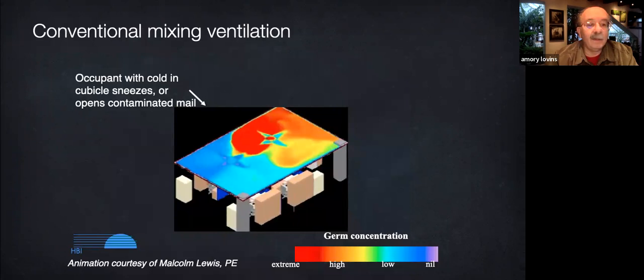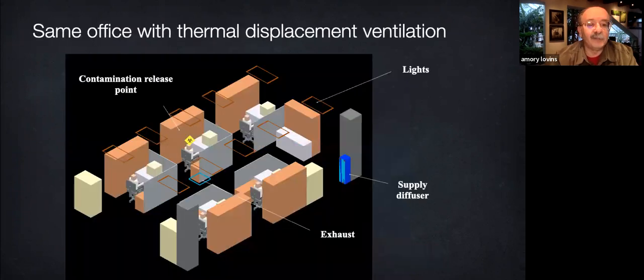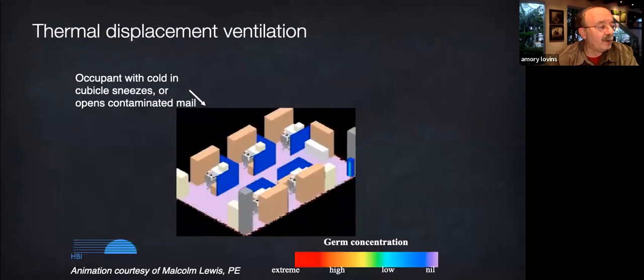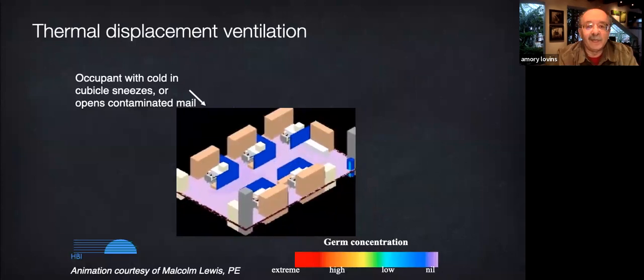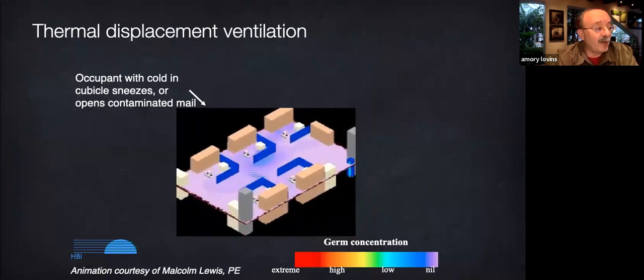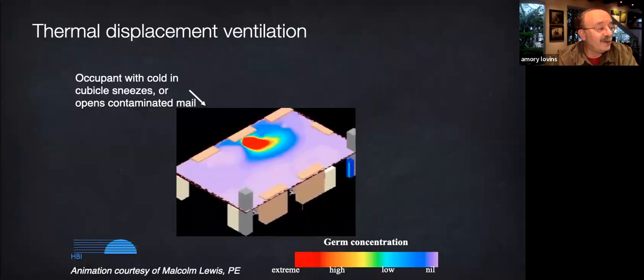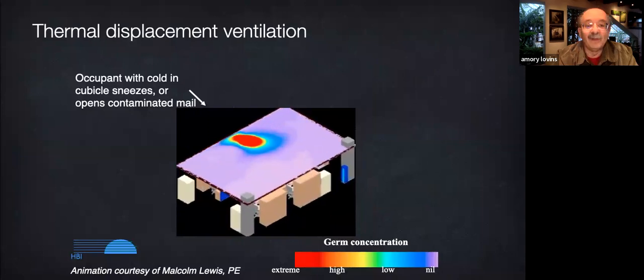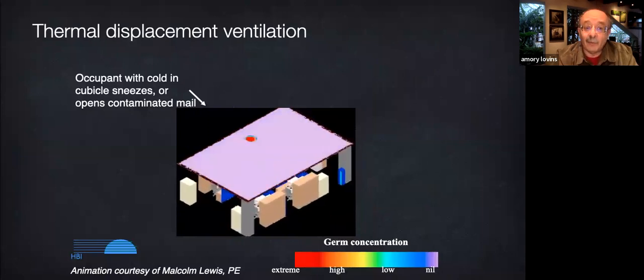Now, in contrast, if fresh air is diffused from low down, even from one corner of the office, like this unimpressive design, the aerosol is quickly carried up and out before it can spread and sicken other workers. Of course, best practice is also to supply 100% outside air. There's the sneeze, but nobody else gets to breathe it. 100% outside air rather than mixing that clean air with dirty air recycled from the exhaust, as most old buildings still do.